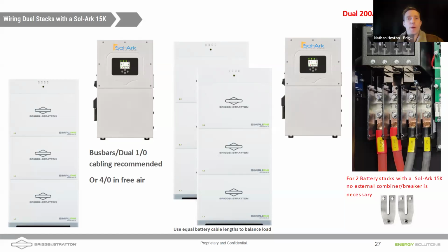So with a 20 kilowatt hour battery, I was using about 15 to 16 kilowatt hours in a given day, and that would back me up for somewhere approaching 30 hours. The average customer uses a bit more than me, and I think the average backup time for a single stack with a 15K is about 15.4 to 15.5 hours.